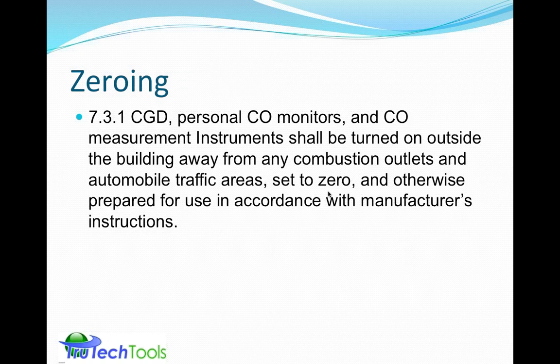We do talk about zeroing of the product, making sure that you have a good reference point for it. The combustible gas detector, personal monitors, and CO instruments shall be turned on outside, away from any combustion outlets, set to 0, or otherwise prepared for use in accordance with the manufacturer's instructions, because they may not always require being set to 0, so you do need to follow the type of instrumentation that you have.